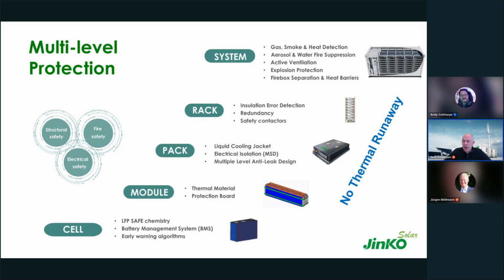In terms of protecting against unforeseen circumstances - the way we put our modules together is different. Modules are different on the PV side than the battery side; on PV a module is a solar panel, but here a module is a group of batteries connected together. We have one module, four modules inside each pack, each module has 12 cells in series, and each pack has 4 of those modules inside it. The pack itself is the core of the battery system.